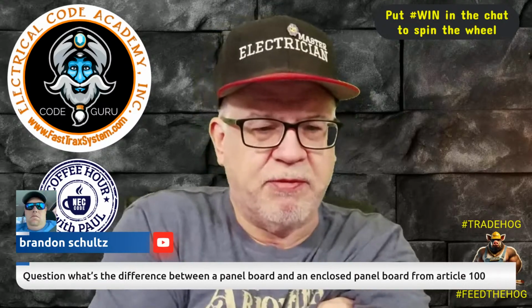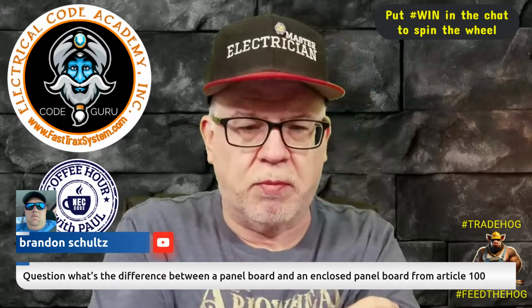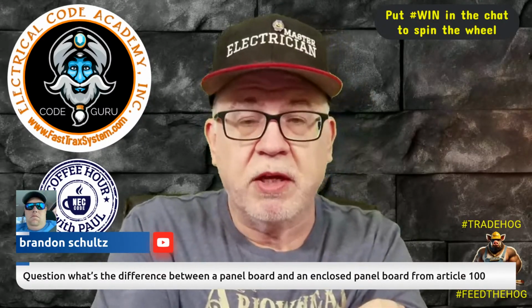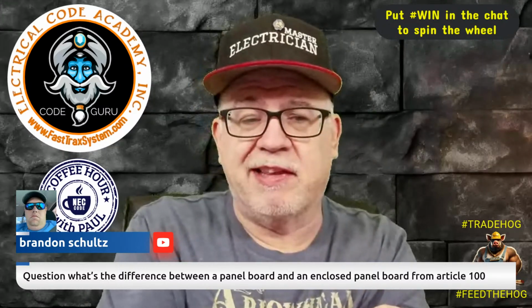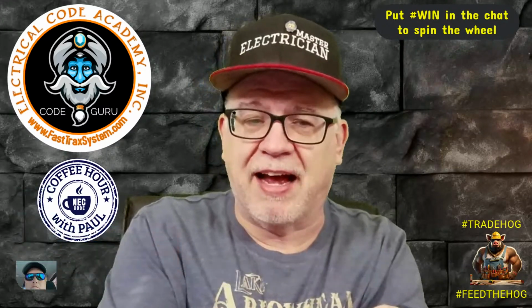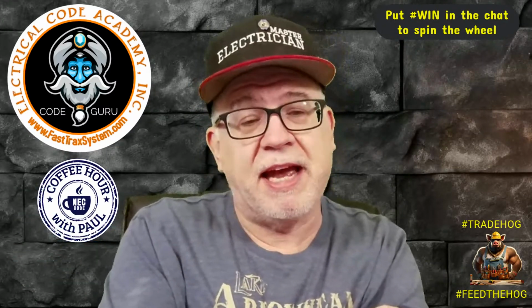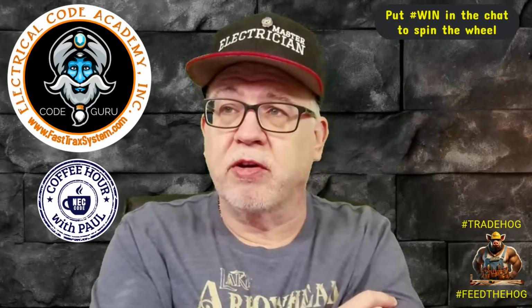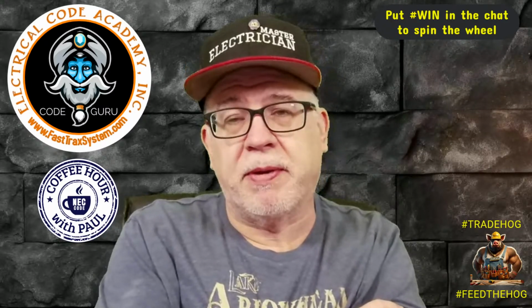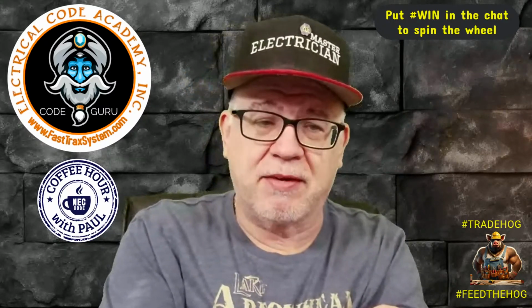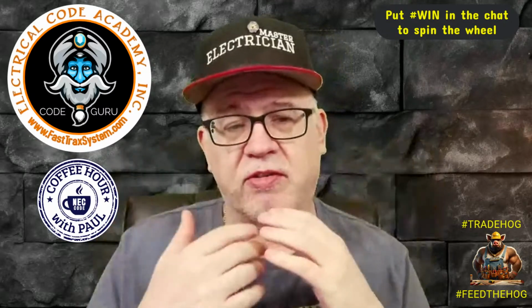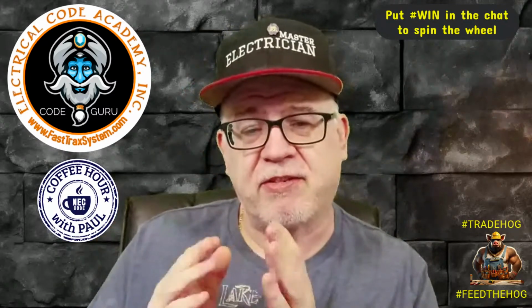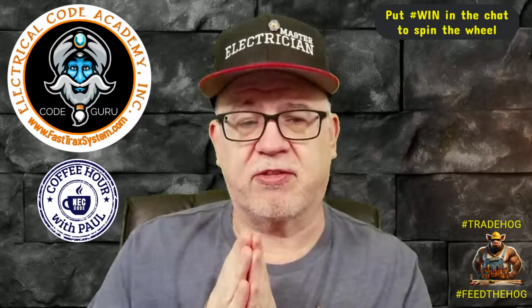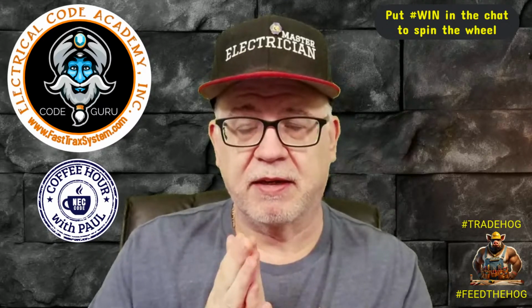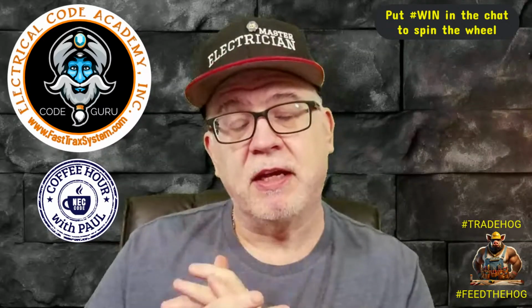Brandon says, what's the difference between a panel board and enclosed panel board from Article 100? So a panel board is actually the guts that go inside of an enclosure or cabinet, whereas you can get an entire assembly where the panel board's already installed inside of an enclosure, so that creates the whole assembly. So panel board in itself is just the guts. That's it, okay? It's just the guts.